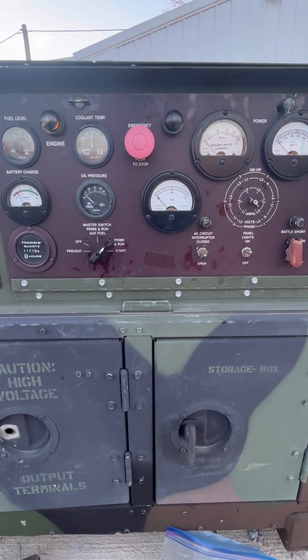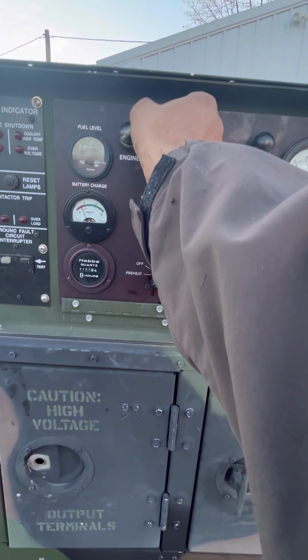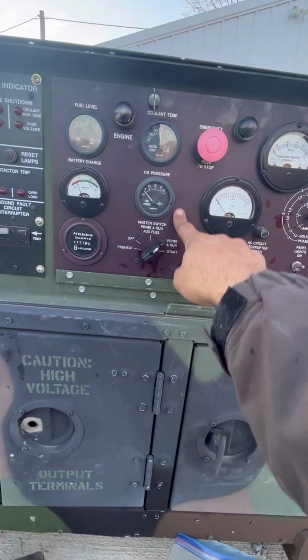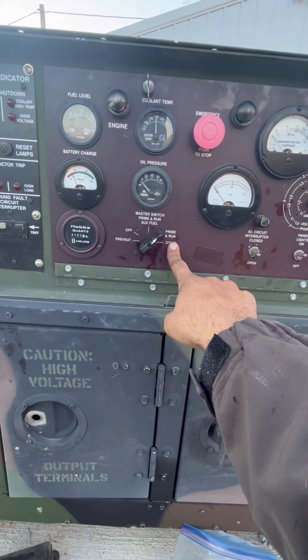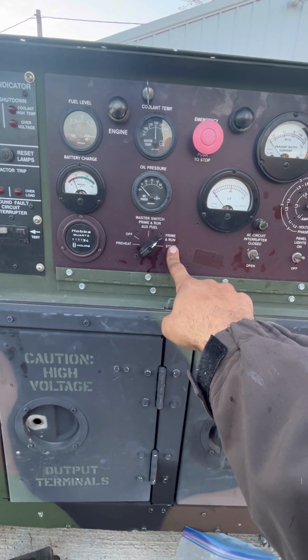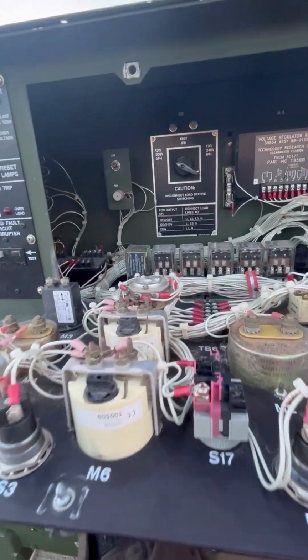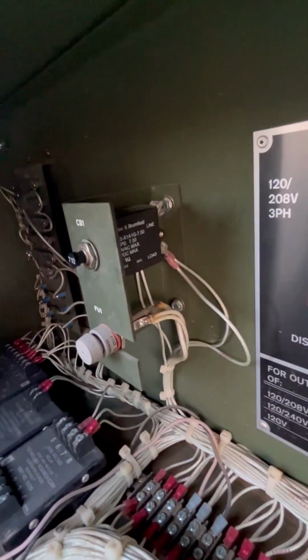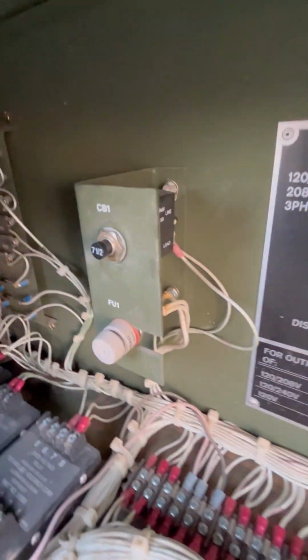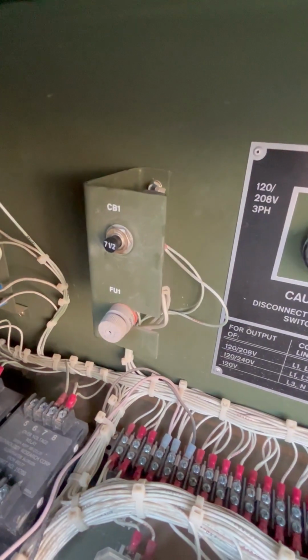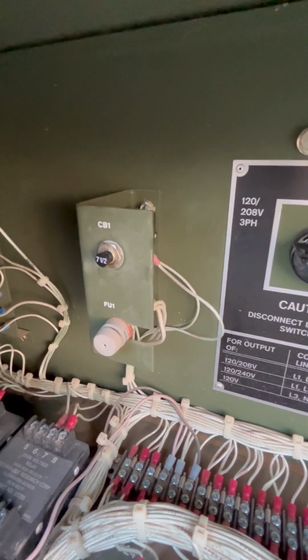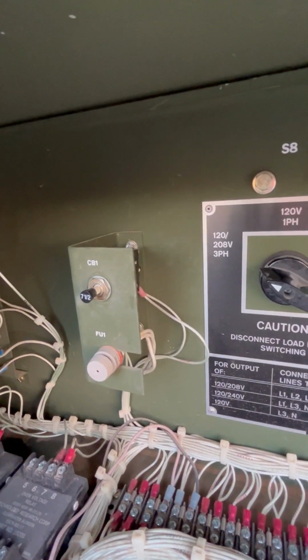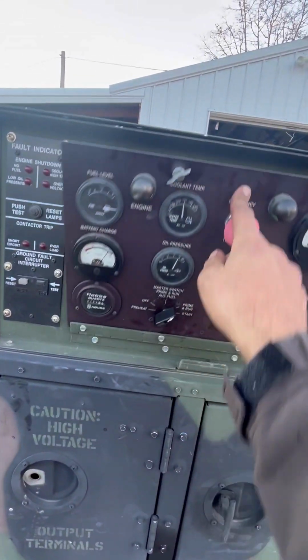I did confirm that the CB1 breaker is tripping almost immediately after you start it. We're on prime run. I don't know if you can hear the fuel pump running. I'm going to start it and you can watch the CB1 breaker trip right here. There it is. She trips right away.